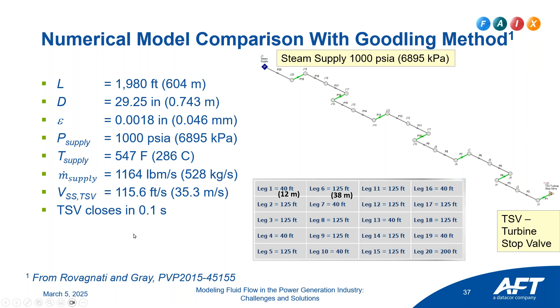So the traditional predictions of the forces - this is leg 1, 4, 7, 10, all the way out, the green legs. Leg 1 is right here, here's 4, 7. So as you get farther and farther away from the stopping valve, these are the forces that happen over time. You can see that on the very first leg, leg 1, the traditional method by an engineer named Goodling - who worked for a firm in Pennsylvania, now part of a larger company - was pretty darn accurate according to the xStream results.